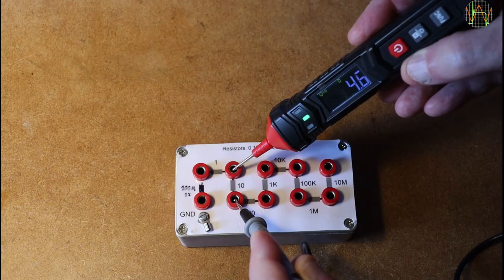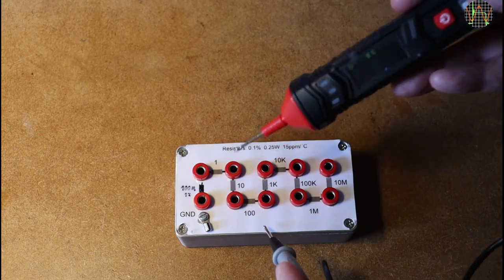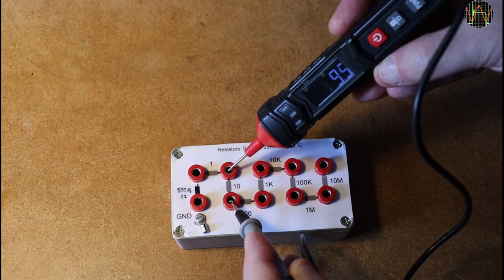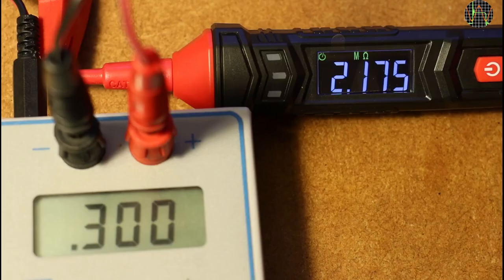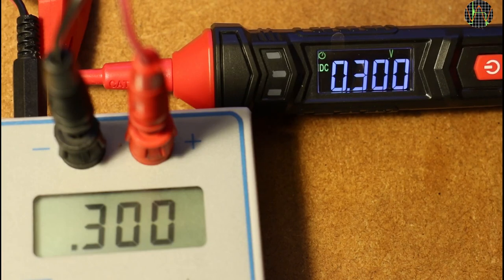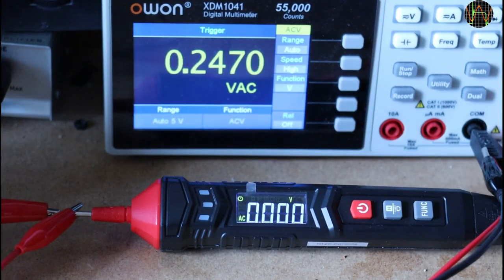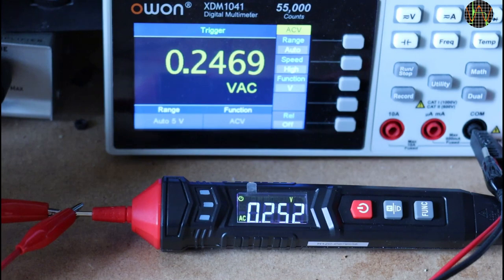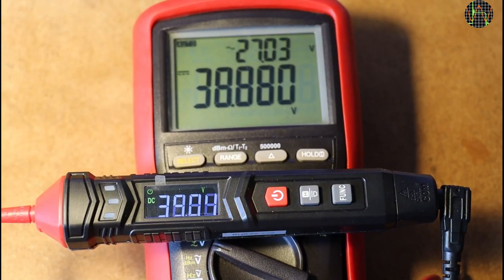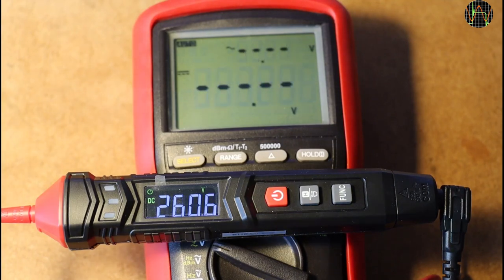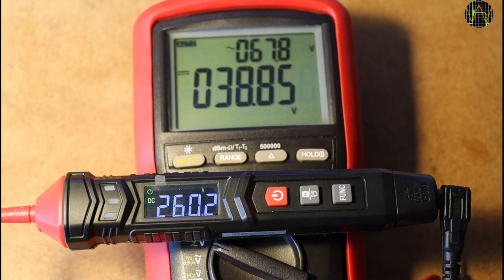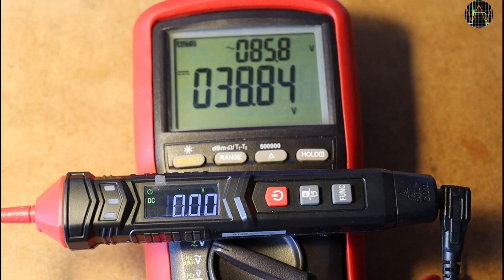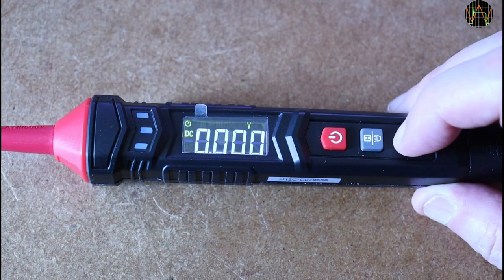When measuring below 100 Ohms in Auto mode, you have to decide whether you are more interested in continuity and beeps or the resistance value in silence and select the mode accordingly. For its intended use, the problems in Auto mode at very low DC and AC voltages are not that much of an issue and if needed you can manually switch to the right mode for low voltages. But beware of mixed AC and DC signals. I don't know how common mixed AC and DC voltages are in electrical installations, they are common enough in electronics, just think of ripple in power supplies, but the ST120 isn't intended for electronics. All I can say, if you have to deal with mixed AC plus DC, the ST120 is not for you. I think that kind of sums it up. If you worry about mixed AC and DC, stay away from the ST120, otherwise it is a nice and affordable tester that doesn't break the bank.